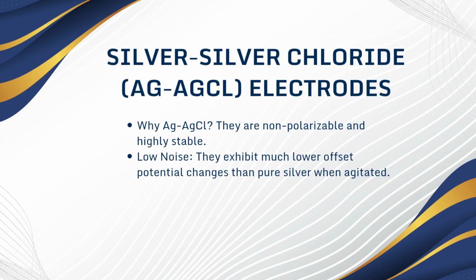The industry standard is the silver chloride electrode. It's highly stable, has a very low half-cell potential, and produces very little noise. This is why you see them used in almost every hospital around the world for ECG and EEG recording.